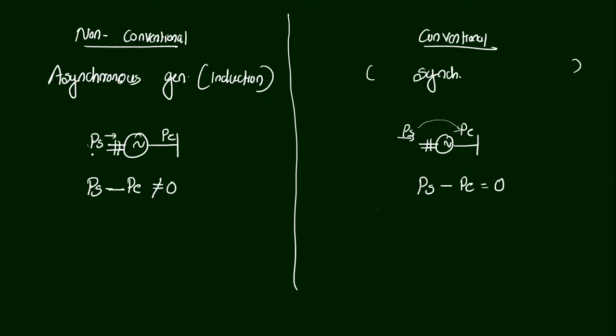The shaft power will be changing always, because in the morning and evening, the wind speed varies - sometimes very high. So the shaft power is changing, and we can't control it. So this power difference will not be equal to 0. But in synchronous generator, the power difference will be equal to 0. So there is a power difference which is called accelerating or decelerating power.